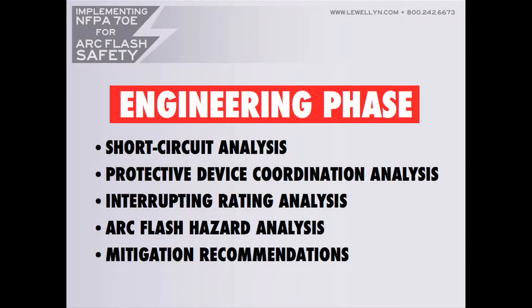They're going to do an interrupt rating analysis. That's where we determine that your breakers will actually do what they say they will do. A 20 amp breaker or a 200 amp breaker also has a ceiling, a top level. Maybe it's 10,000, which is what your home is, maybe it's 100,000. What those mean is that if let's say it's 20,000, but we calculate you have 30,000 amps of current, that breaker may not trip. It might weld together, it might blow up.